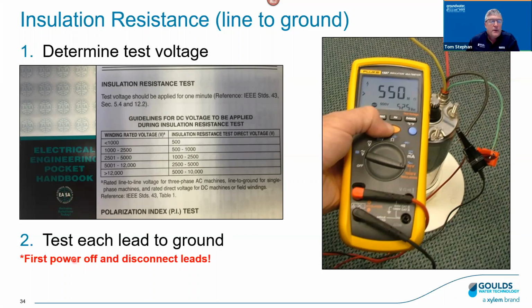I do my test. So we're going to test each lead to ground. Right, again, this is no power, the power is off, and they're disconnected, right? So in this case, again, I've got it back on the workbench. I'm just looking at that motor itself, and I've got to test each hot lead to ground. So in this case, I've got a 3-wire, so I've got a black, a yellow, and a red. So this is just showing one. And I'm set to send 500 volts. I press, hold, and release. And now I get 550 megohms, 550 million ohms, right? Well, one thing that we know is that this meter is pegged, it's maxed out, which is good, right? With this sort of test, you have no internal connection. Your windings are in good shape. They're not grounded inside the motor.